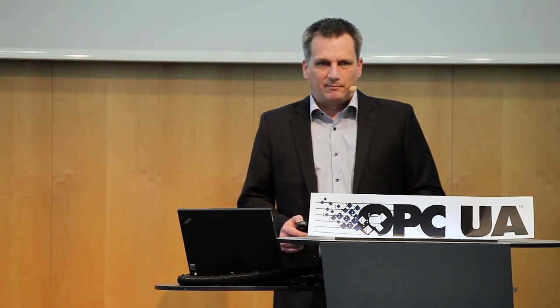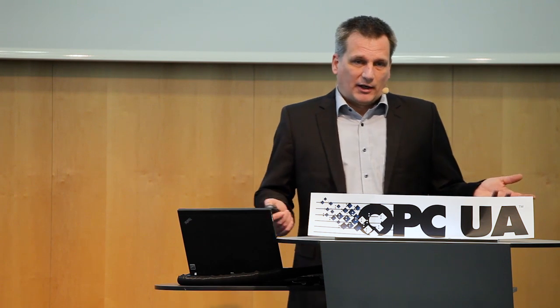And of course, we have the data change mechanism. Most people know from the classic OPC, this is now called subscription, and the subscription has monitored data, and this data is transferred when the data is changed. So we only transfer the data when the data has changed. We don't need to cyclically transfer the same data all the time, because we already know it. And the same mechanism we, of course, use for events. So the notification is only transported over the wire when it actually occurs.